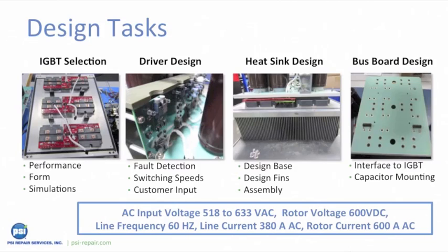The third step is heat sink design — providing adequate surface area for the anticipated heat load while maintaining continuity of the physical installation requirements. The existing design can be a starting point, and any additional heat dissipation efficiencies help create a longer-lasting product. We also look for opportunities to reduce manufacturing cost. The last step is bus board design: the new bus board must interface to the new IGBTs, provide clearances for mounting bus capacitors and driver boards, line up perfectly with the rigid bus bars in the existing controller, and be designed to avoid condensation pooling issues seen at some locations.